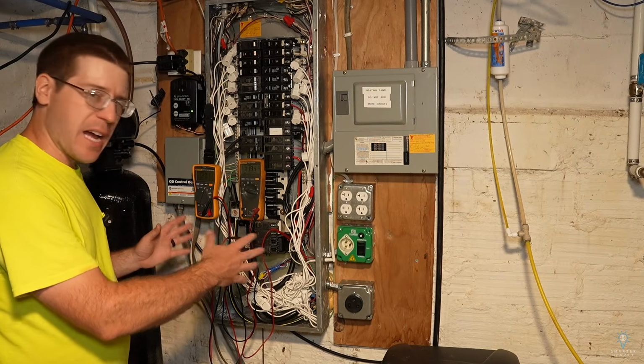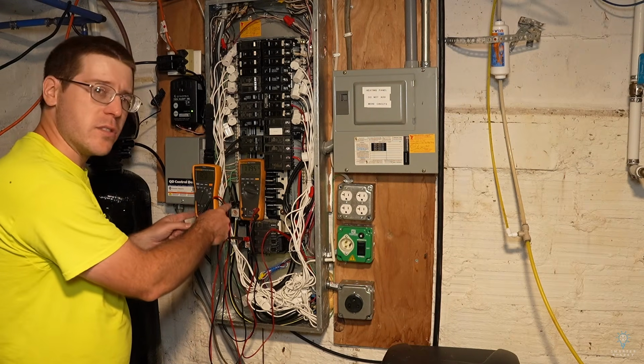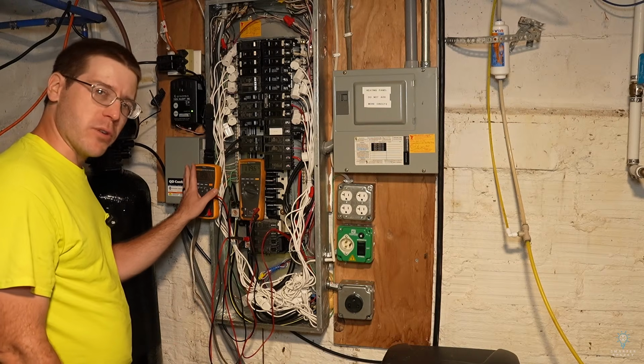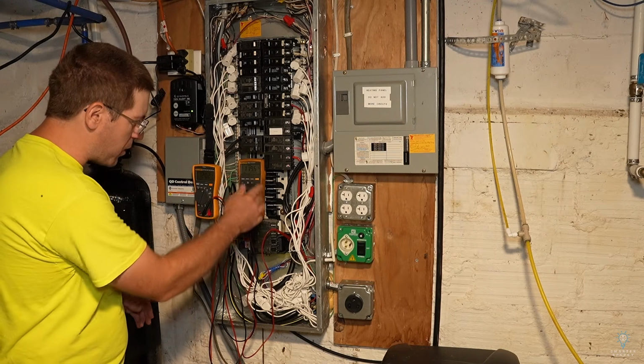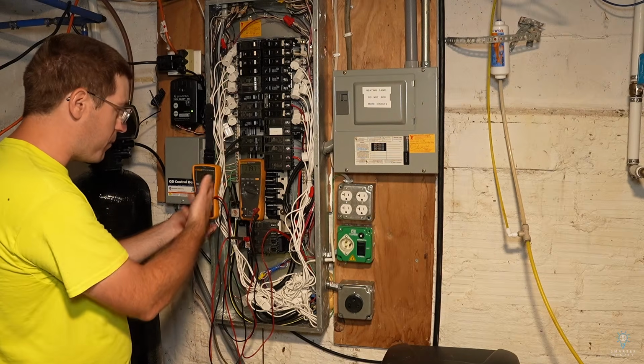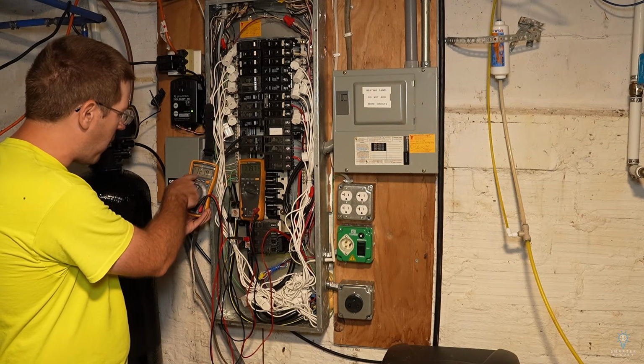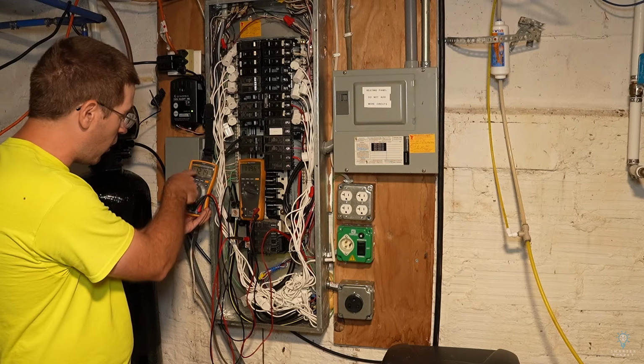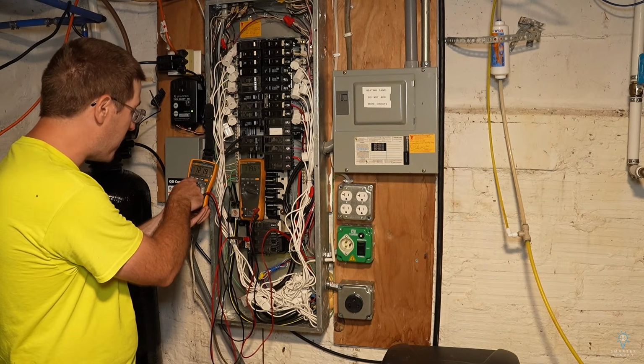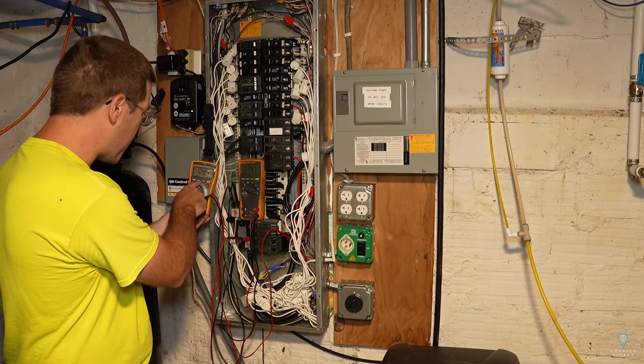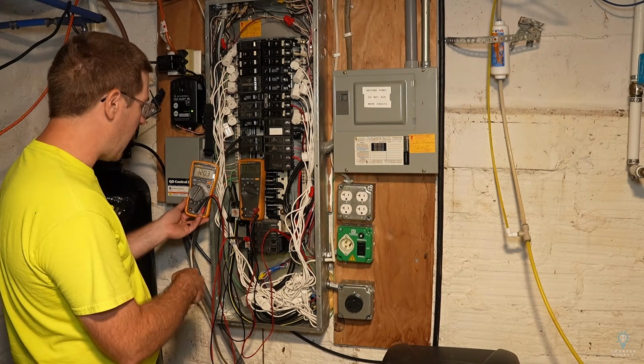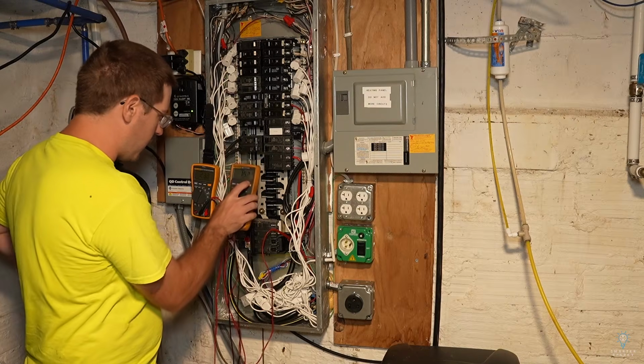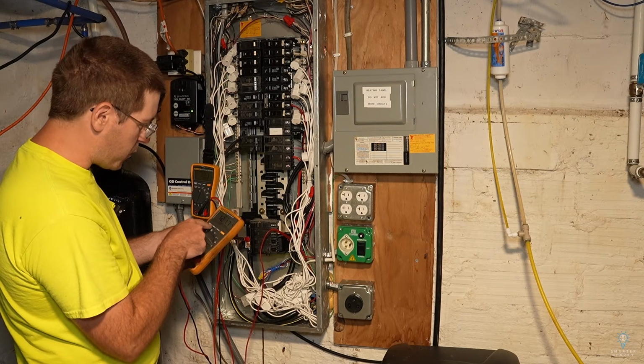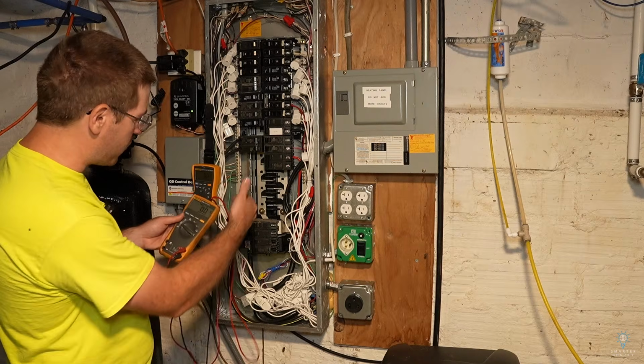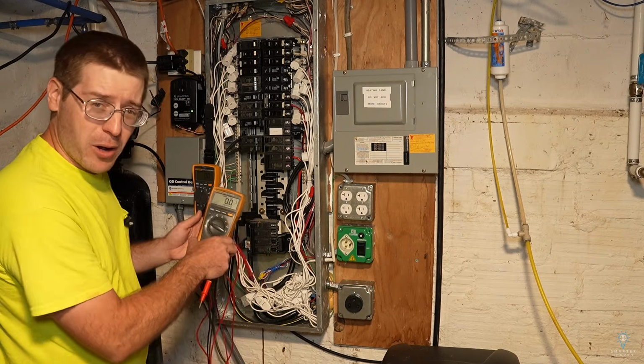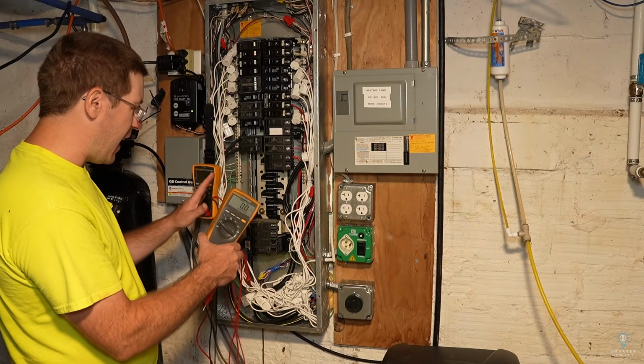So I just cleaned everything up outside, got that panel all buttoned up, and before I did that, I set these two meters up here in min-max mode. This is measuring the voltage from line 1 to neutral, and this one's measuring the voltage from line 2 to neutral. And again, they've been set up for min-max, so if we take a look over the last hour, the max voltage from line 1 to neutral has been 121.9 volts, and the minimum was 117.6 with an average of 120.4, and it's currently at 120.3. If we take a look at this meter, shoot, I just lost the minimum I guess now, but the max was 121 volts, and the minimum on this before I dropped the lead out of the terminal there was about 117 as well. So it's looking like everything is balanced now.